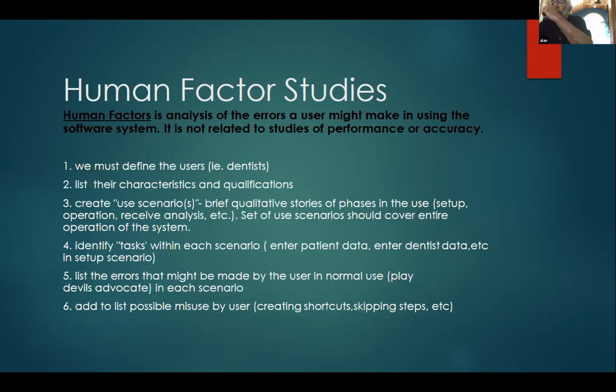You have to create a use scenario: brief qualitative stories of phases in the use. Setup, operation, receive analysis, etc. The set of use scenarios should cover the entire operation of the system. You should identify the tasks within each scenario, and enter the patient data, enter the dentist data, etc. List the errors that might be made by the user in normal use. Play devil's advocate in each scenario, and add to the list possible misuse by the user, such as creating shortcuts or skipping steps.